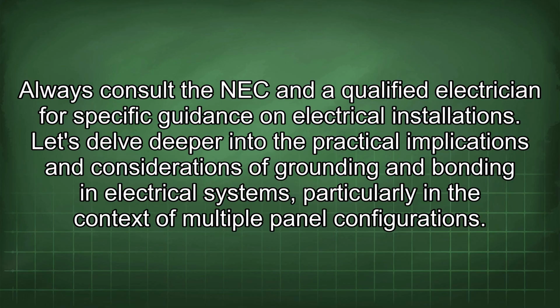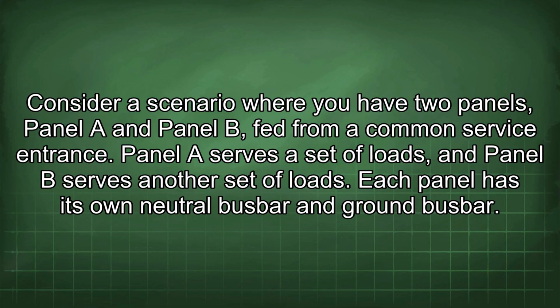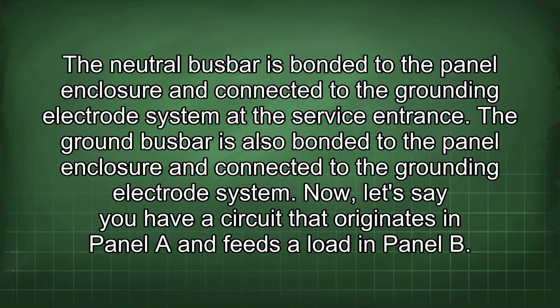Let's delve deeper into the practical implications and considerations of grounding and bonding in electrical systems, particularly in the context of multiple panel configurations. Consider a scenario where you have two panels, Panel A and Panel B, fed from a common service entrance. Panel A serves a set of loads, and Panel B serves another set of loads. Each panel has its own neutral busbar and ground busbar. The neutral busbar is bonded to the panel enclosure and connected to the grounding electrode system at the service entrance. The ground busbar is also bonded to the panel enclosure and connected to the grounding electrode system.